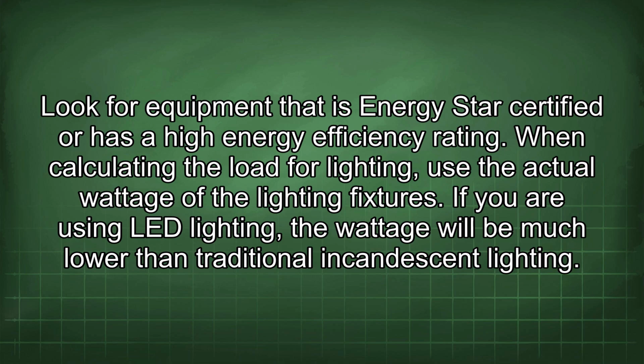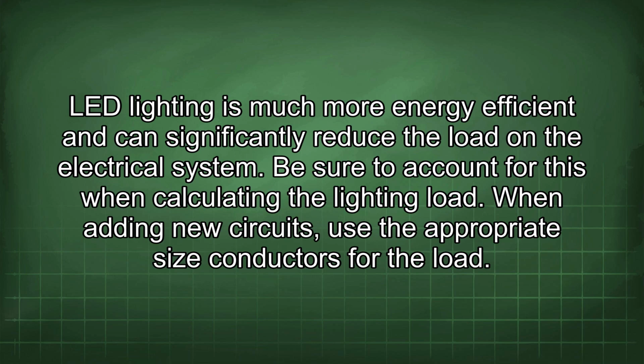When calculating the load for lighting, use the actual wattage of the lighting fixtures. If you are using LED lighting, the wattage will be much lower than traditional incandescent lighting. LED lighting is much more energy efficient and can significantly reduce the load on the electrical system. Be sure to account for this when calculating the lighting load.